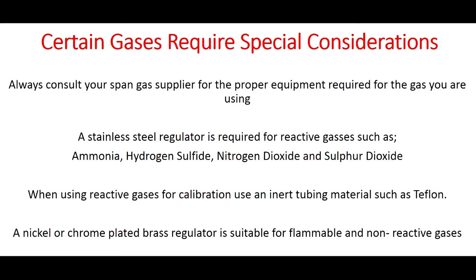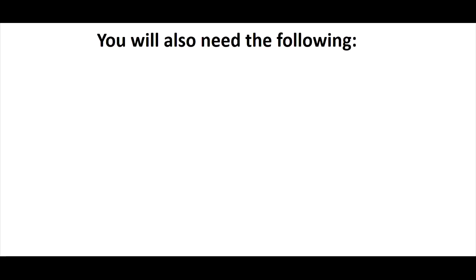A stainless steel regulator is required for reactive gases such as ammonia, hydrogen sulfide, nitrogen dioxide, and sulfur dioxide. When using reactive gases for calibration, use an inert tubing material such as Teflon. A nickel or chrome-plated brass regulator is suitable for flammable and non-reactive gases.